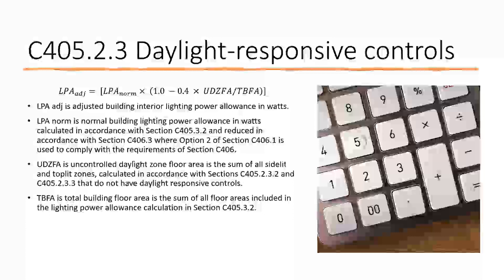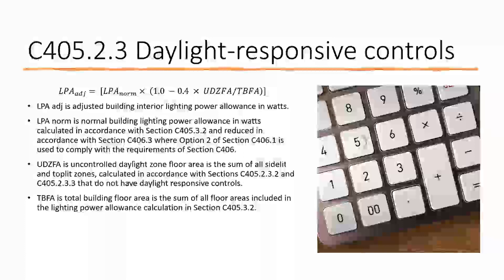The UDZFA is the uncontrolled daylight zone floor area — there could be some areas where you have daylight zones that are required to be controlled, and those are not included in this calculation. The TBFA is the total building floor area — the sum of all floor areas included in the lighting power allowance calculation. Probably the first thing to do is calculate all your daylight zones, figure out that number, apply it in and then figure out which are absolute and which are optional. If the adjusted LPD is less than your normal lighting power value, then you don't have to have daylight responsive controls.